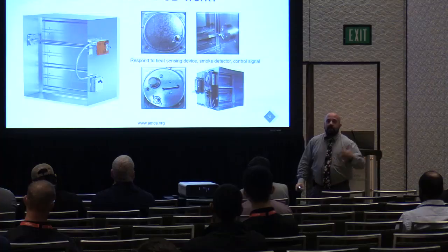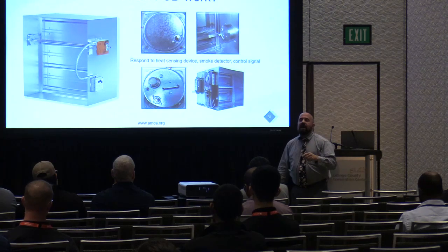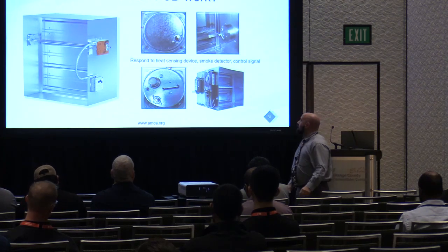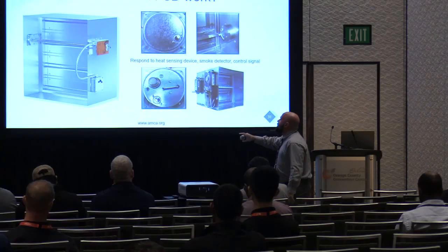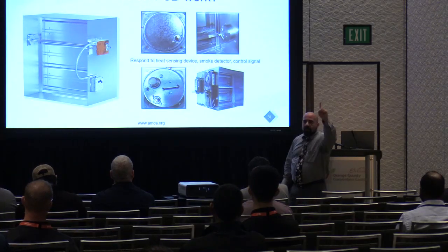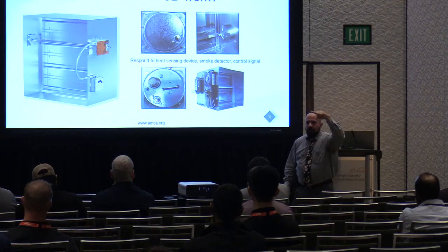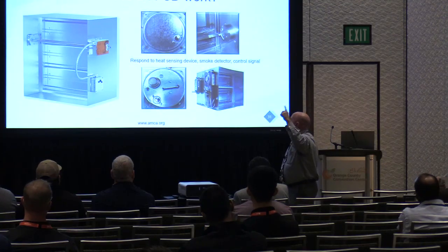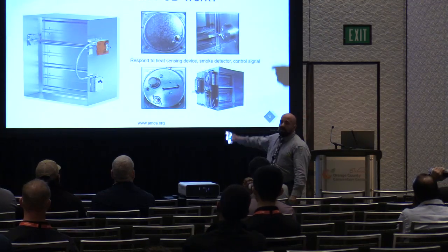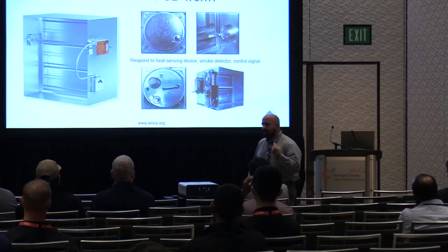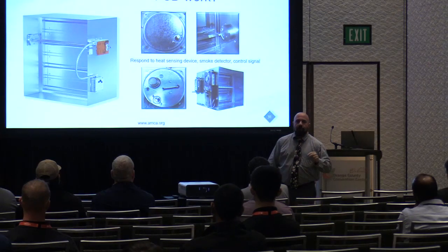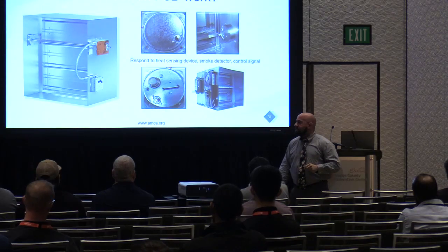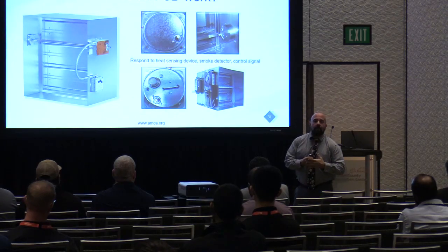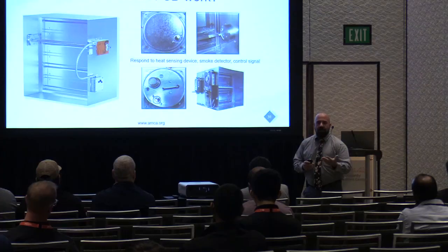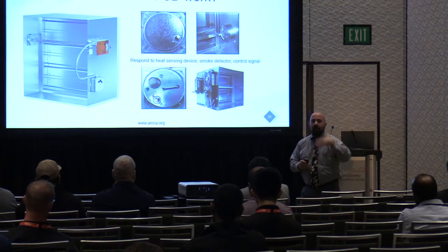It could have a smoke detector, it could sense smoke, it's wired in series with the actuator, it'll cut power and do the same thing. Right? So we have a couple different types of heat sensing devices. There's single temperature devices. Could be 165, 212, 250, 350. There's dual temperature devices. For a fire smoke damper that's intended for use in an engineered smoke control system, this gives you reopenable control. You'll set a low limit, 165, on the fire smoke damper. You'll set a high limit, 350.